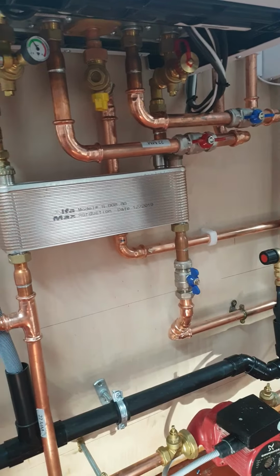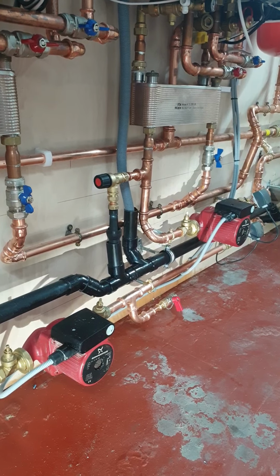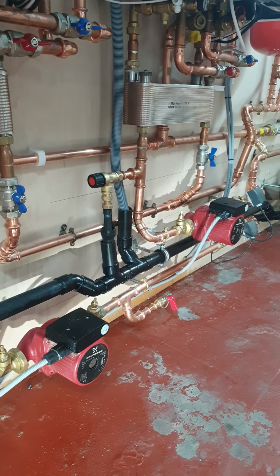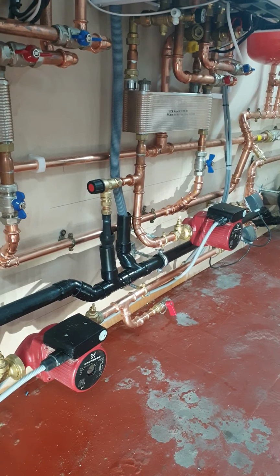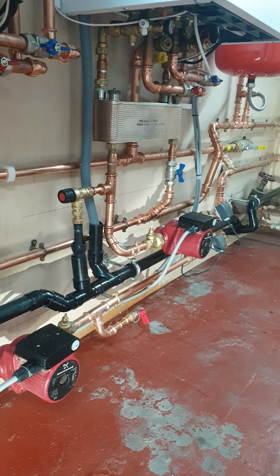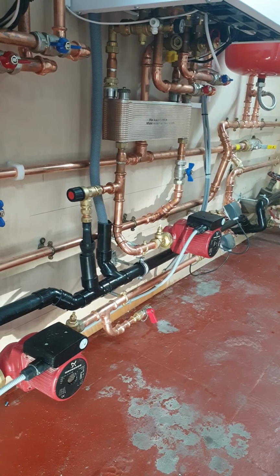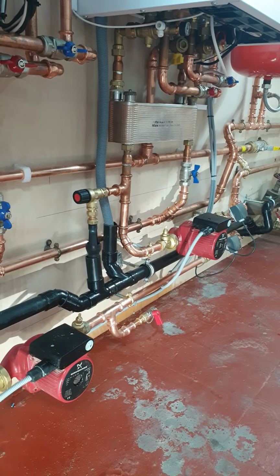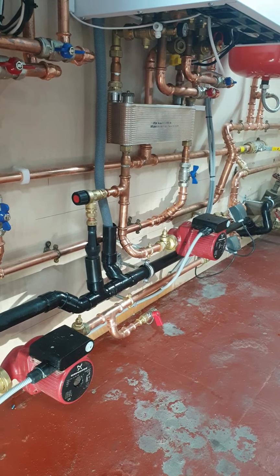I've got two pumps pumping in parallel. So these are 2580s. So I've got double the flow and a maximum of 8 meters head available for those pumps. The building is about 30 meters high, and the pump head has got nothing to do with the height of the building. So for those that tell me it is, try and explain to me why the heating is working on the top floor of this block with an 8 meter head pump. Mr. Combi, if you're listening, my radiators are not within 8 meters of the pump. So there you go, looking good.